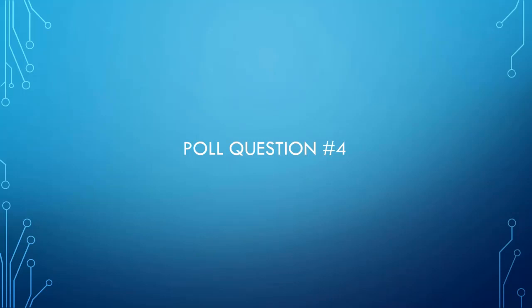Here's another question. Other than oil gas analysis, what PMs do you recommend for oil filled transformers? That's a great question. Inspection of the gauges for sure. And more manufacturers are, let's face it, we live in a smart world now with the Internet of Things, and the gauges are more and more getting at least contacts or analog outputs so that a building DCS or some sort of PLC can monitor that transformer, depending on the size of it. Certainly a transformer differential relay could help with that.